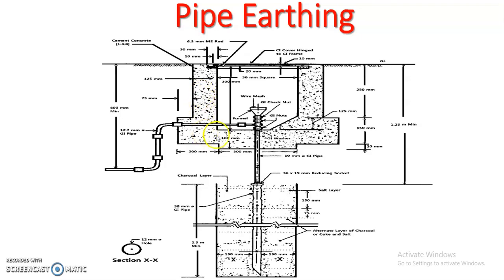Again with the help of cement concrete, this is our cement concrete. So we can use cement concrete in order to protect this earthing. So this is our CI frame, which is hinged at the top. This is our ground level. So by using pipe earthing, this GI pipe has a number of holes. We can connect a number of terminals or a number of equipments to this earthing in order to protect that equipment. So we have to use pipe earthing in case of our pole mounted substation.